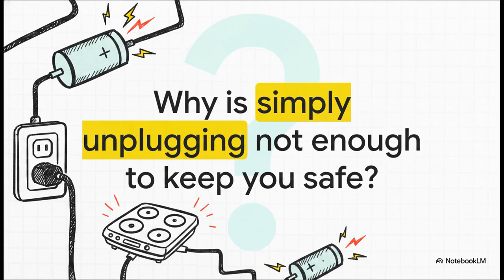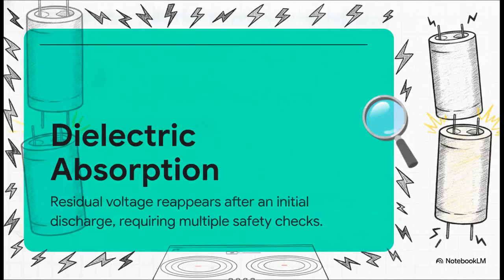Well, wrong. The hidden danger inside these units lies in the large electrolytic filter capacitors. They can hold massive electrical charges long after the power cord is pulled. And this brilliantly illustrates why patience is absolutely key here. There's this phenomenon called dielectric absorption. Even if you think a capacitor is totally discharged, its internal dielectric material can retain a sort of memory, causing a dangerous residual voltage to literally reappear at the terminals after a few minutes. These large capacitors are super sneaky, so treating them with respect is just non-negotiable.